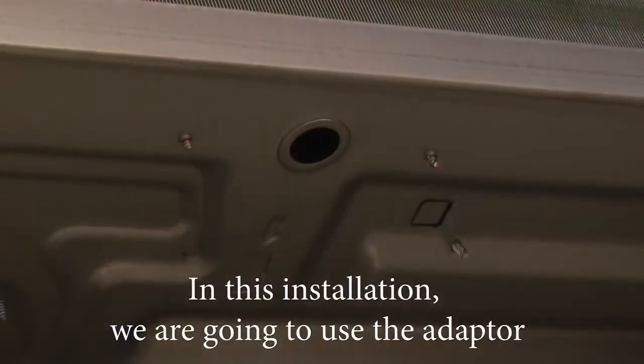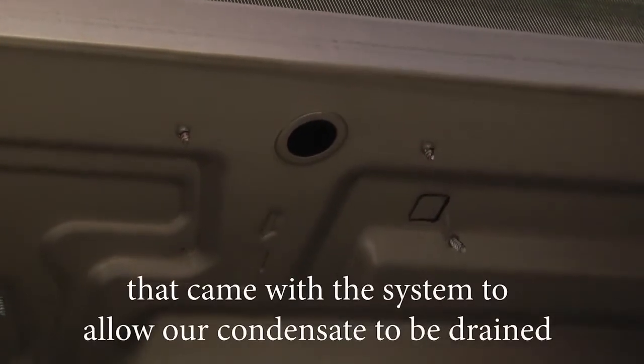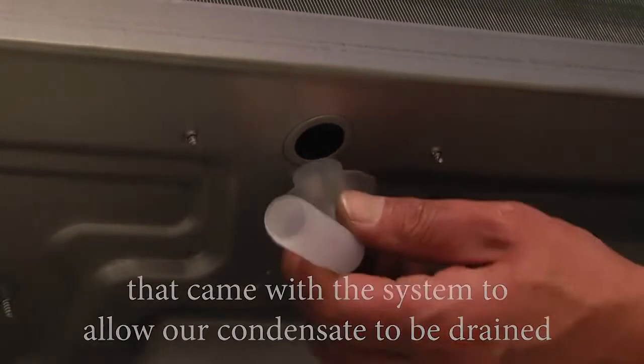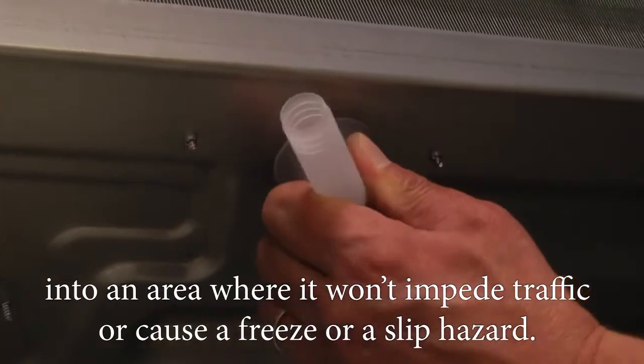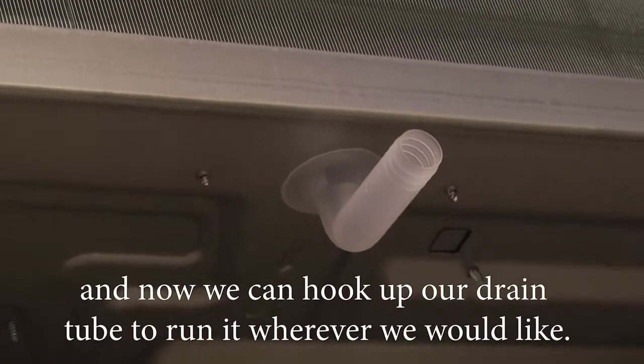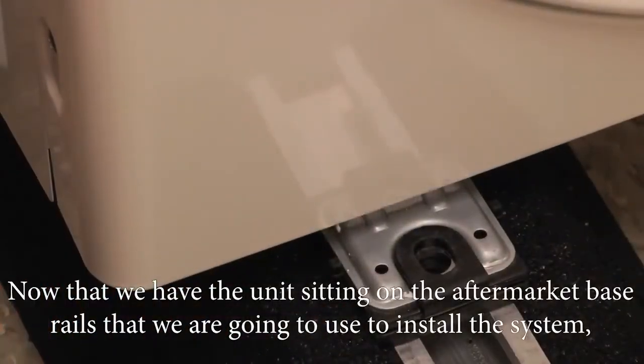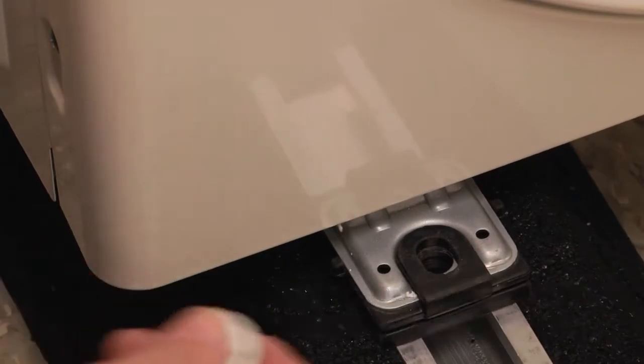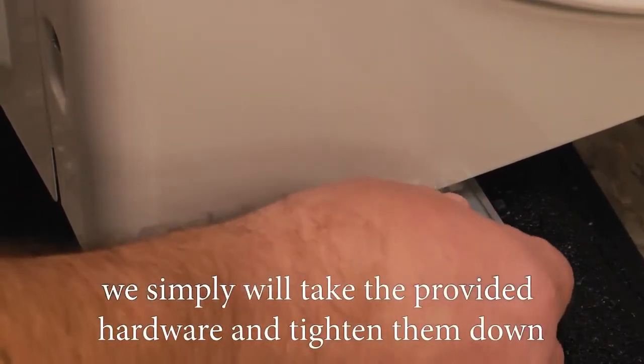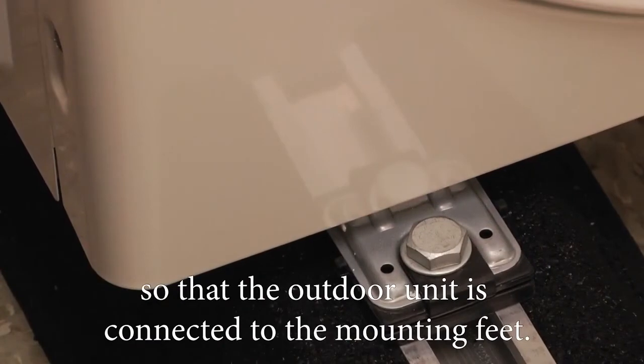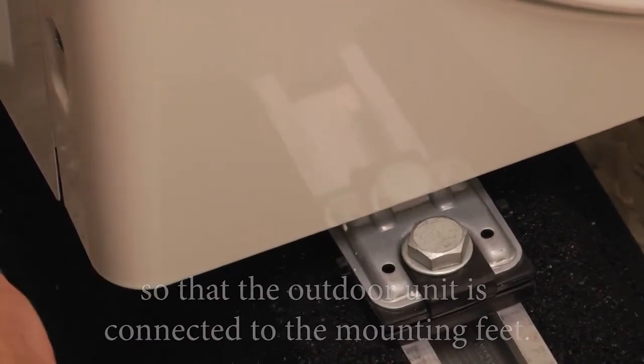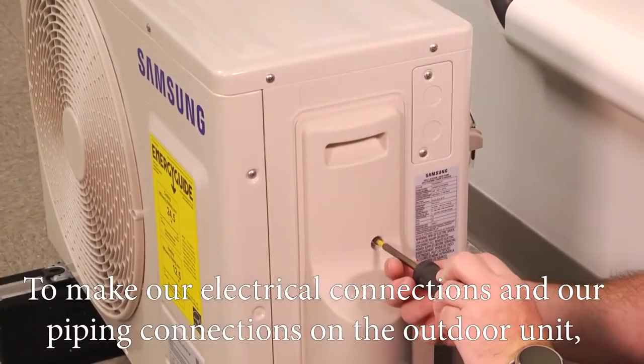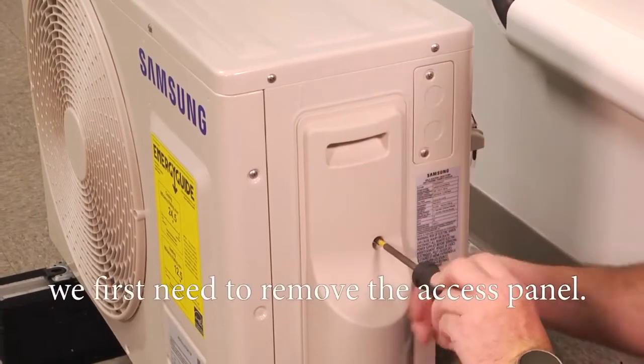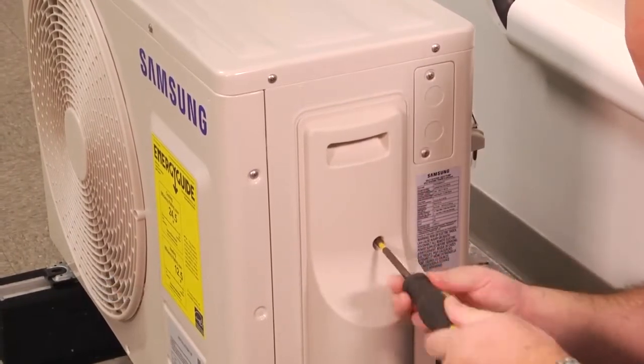In this installation, we're going to use the adapter that came with the system to allow our condensate to be drained into an area where it won't impede traffic or cause a freeze or a slip hazard. It simply snaps into the bottom, and now we can hook up our drain tube to run it wherever we'd like. Now that we have the unit sitting on the aftermarket base rails that we're going to use to install the system, we simply will take the provided hardware and tighten them down so that the outdoor unit is connected to the mounting feet. To make our electrical connections and our piping connections on the outdoor unit, we first need to remove the access panel.